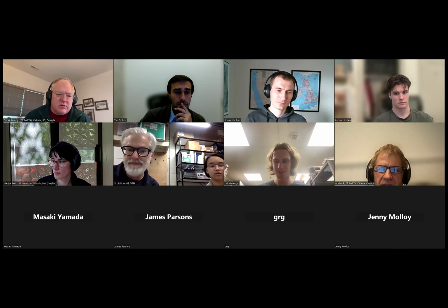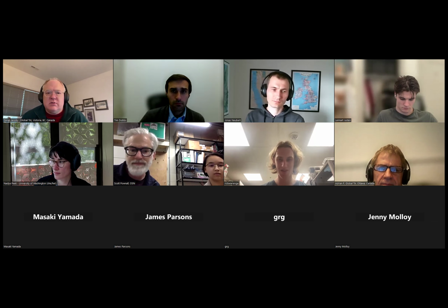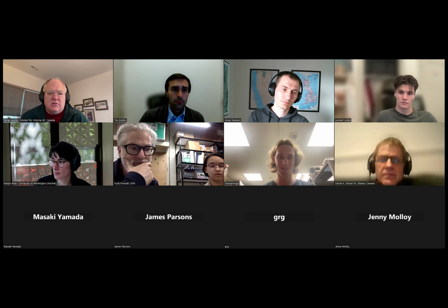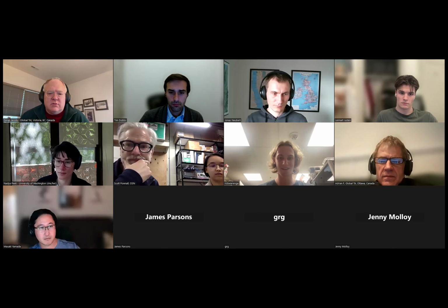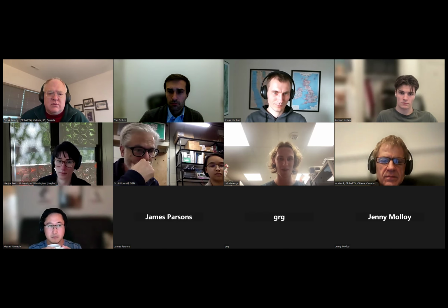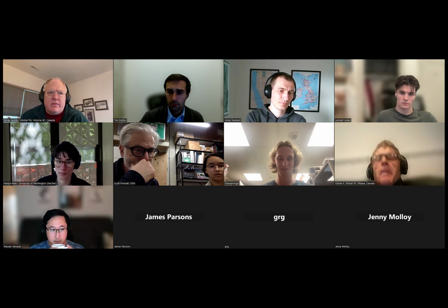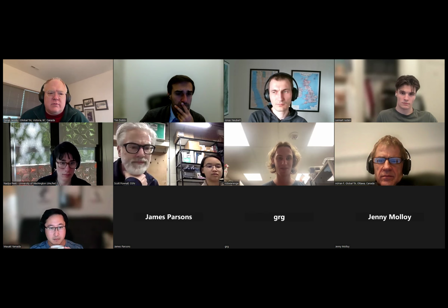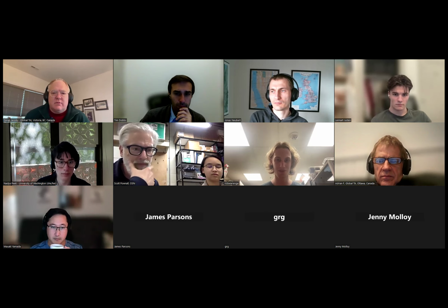Sure. So I'll very briefly give a general description of PyLab Robot and then talk about how you can use it for OpenTrons. PyLab Robot is an open source hardware and OS agnostic interface to lab automation devices. We have universal interfaces for liquid handlers and also other machines like pumps and scales, where you can use the same API to aspirate, dispense, pick up tips, etc. And then there are different backends that translate this to commands that specific robots understand, such as Hamilton robots, Tecans, and also OpenTrons.